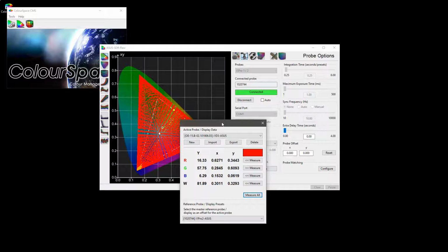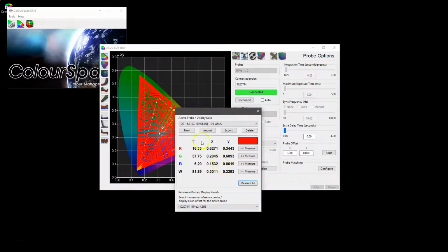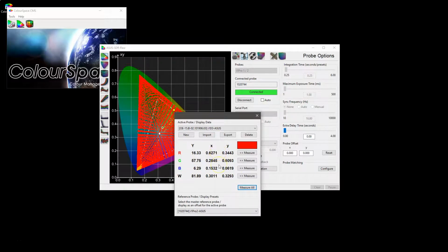This gives us the ability to be very accurate on displays that very specifically are non-additive, and that is most commonly the WOLEDs, where there is an additional white pixel. So this compensates for the issue there. But the FCVM method is so accurate across the board that we use it for everything, and we do not use FCMM at all. There is an additional method for doing probe matching though, and that is multi-point matching, where we can actually use a cube-based set of values rather than just the 4 colors we see here.